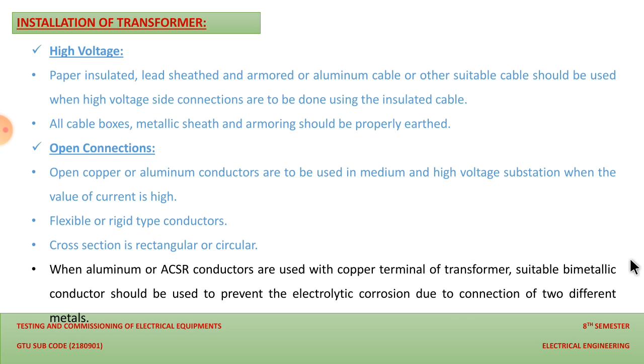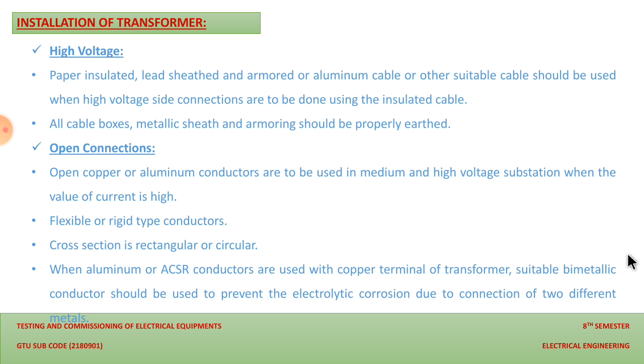And when aluminum or ACSR conductors are used with copper terminals of the transformer, a suitable bimetallic conductor should be used to prevent electrolytic corrosion due to the connection of two different metals. Generally when we connect two different metals, corrosion of the material will take place. So we should keep that in mind when we use the ACSR conductor with the copper terminal of the transformer.